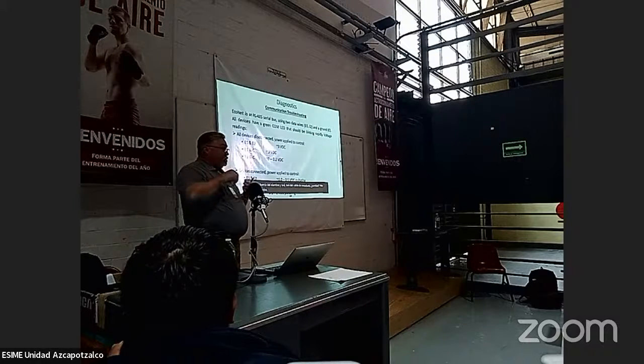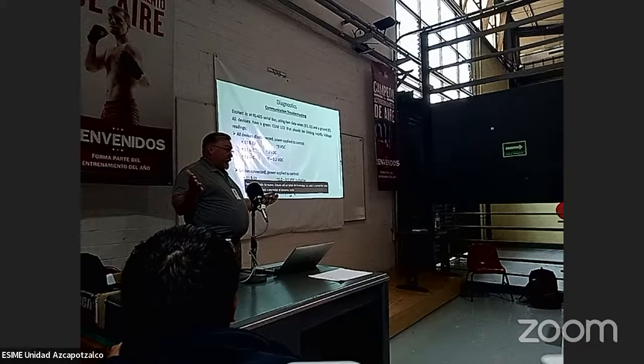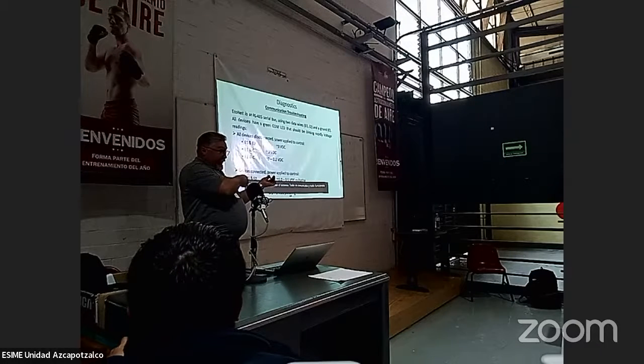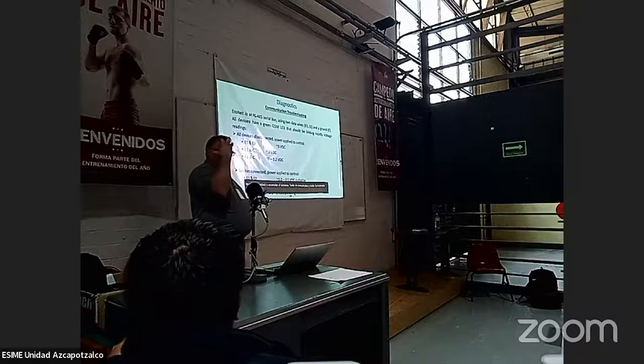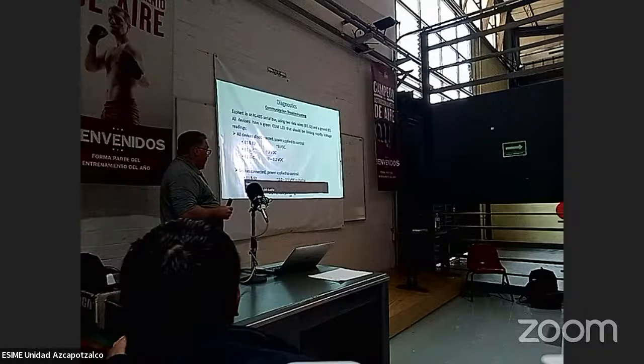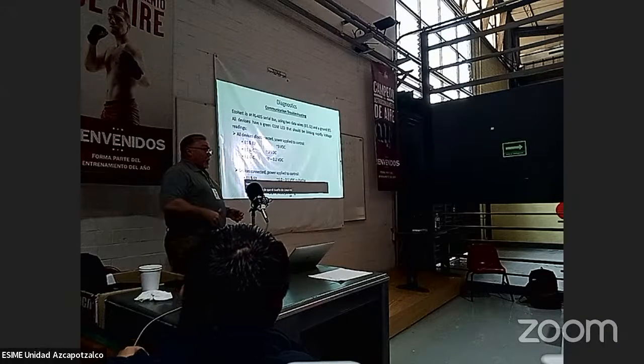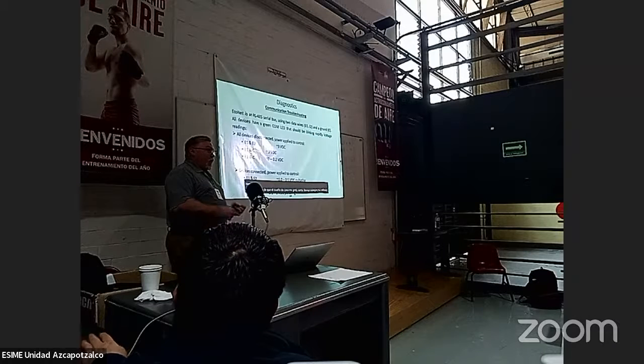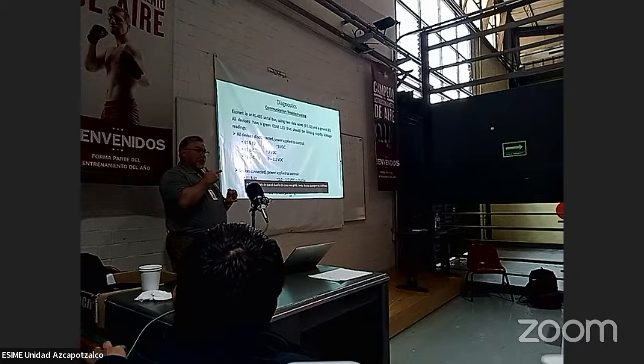Rewired everything back up. I was there about a total of 8 minutes. Wired it back up, went upstairs, turned the system back on, everything communicated, and everything operated fine. I yelled at him after the homeowner yelled at me, right? Always check your wiring. A lot of times you'll find that the wire is broken or it's loose, right? Make sure your connections are proper before you get them aboard.